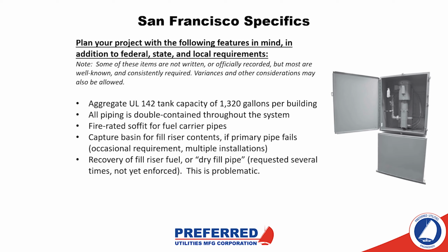But the most problematic aspect of this is that in order to recover that fuel, it is going to have to be contained by the owner of the building. Once it's contained by the owner of the building, it can be pumped and used in the system later. But that means that it needs to be contained in the meantime. The reason is because most truck delivery operators or owners will not allow customer fuel back into their trucks.